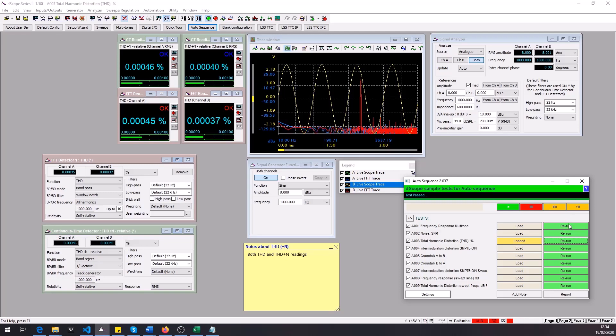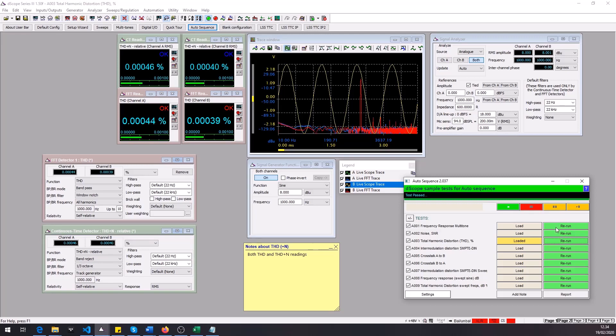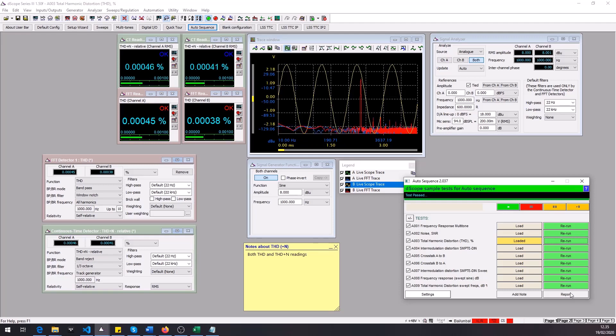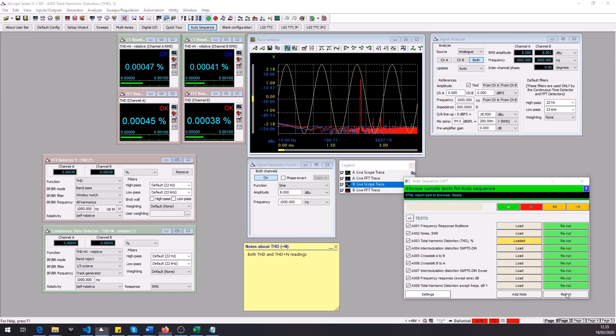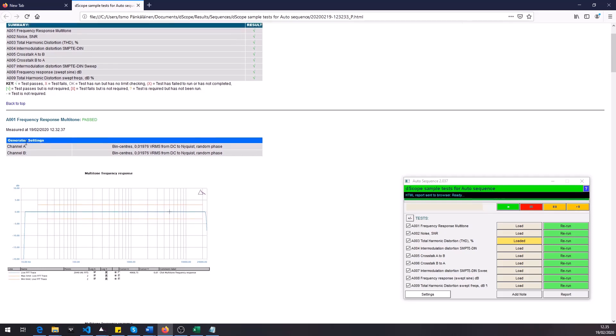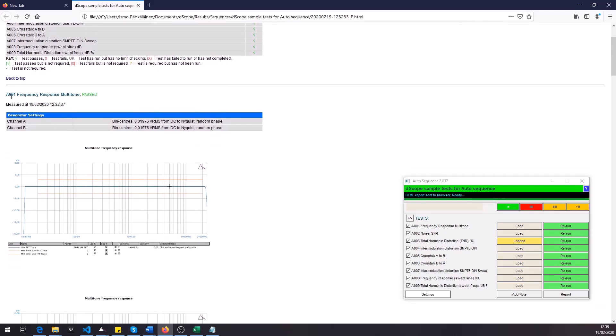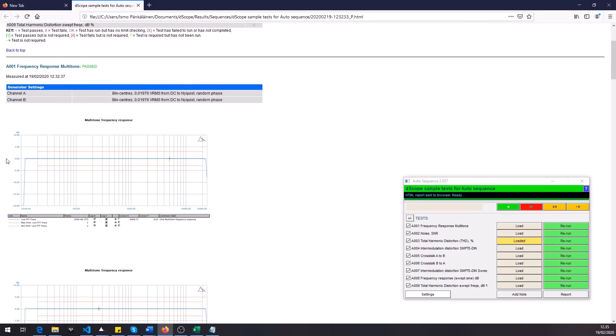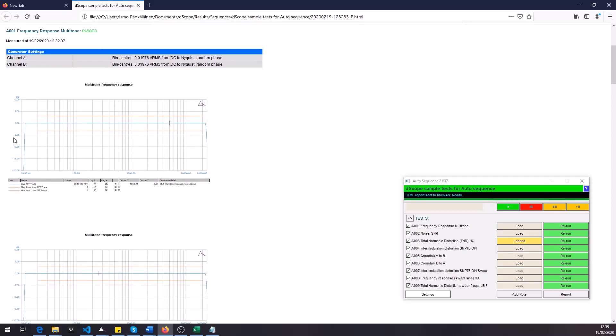So all green, we passed all the tests. Like I mentioned, the auto sequence tool collects all the results so now we actually have a ready-made HTML report which we can access by clicking here on the report button. So clicking it, it takes us to the report. In the beginning you got the summary, you got all the tests setups listed here and the results, each one passed.